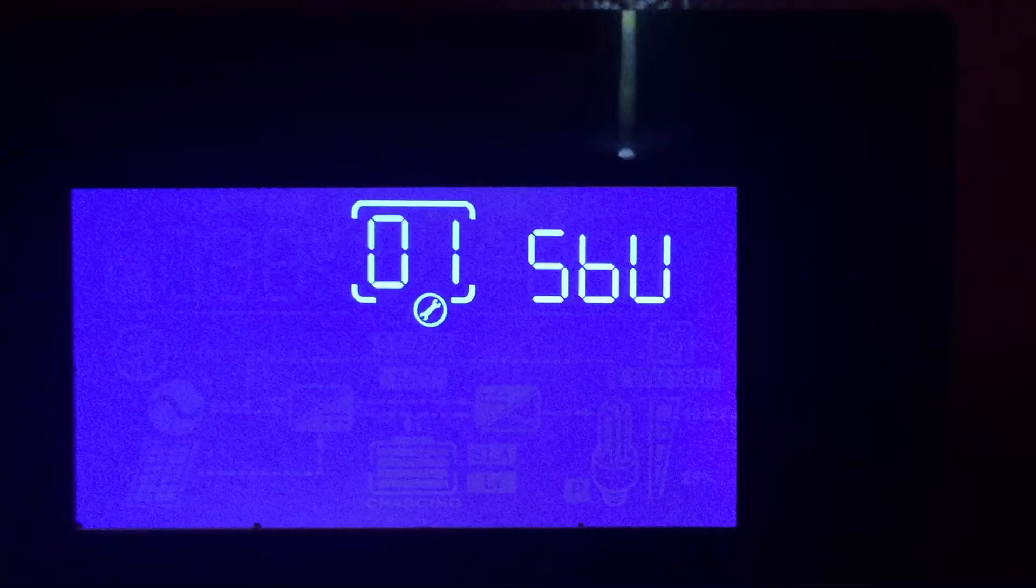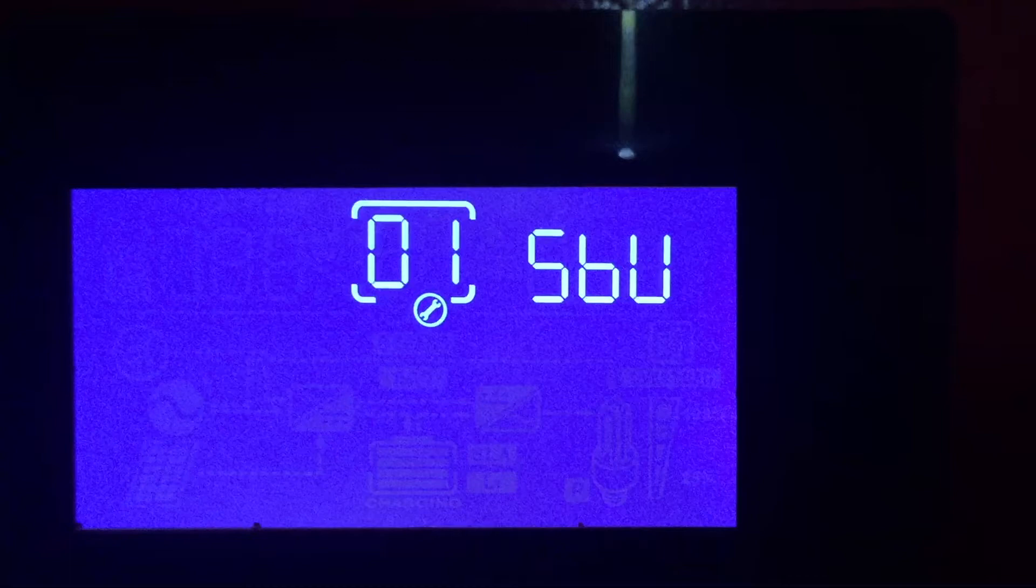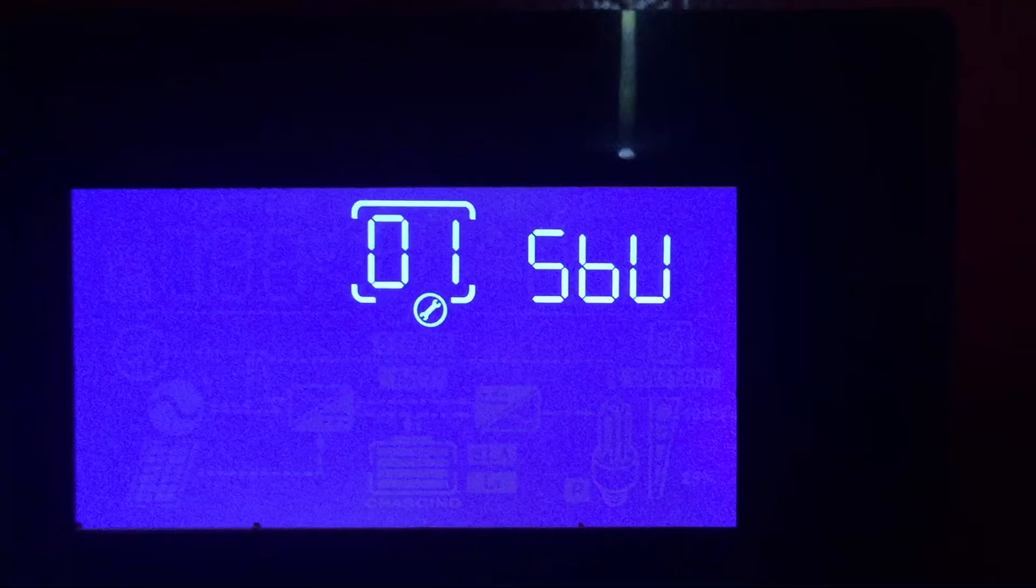In SOL mode when you have that programmed in that manner, once your PV arrays are not producing any solar it automatically goes back into utility. It's the same as if you reach the point on your programming on number 12. If that also goes below that value it will also go back to utility. On SBU however it will force the unit to use the battery first before it goes to utility.